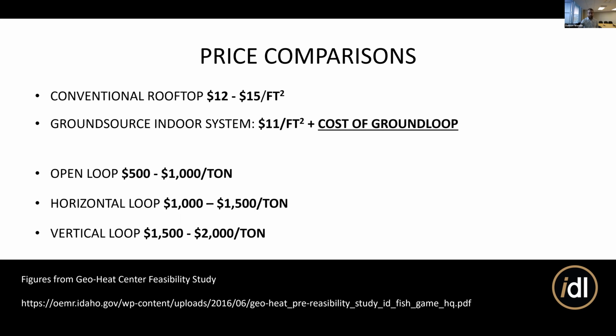A horizontal loop, those slinky systems that can be spread out at 6 to 10 feet underneath the ground, those were $1,000 to $1,500 per ton. And then the vertical boreholes were $1,500 to $2,000 per ton. The highest energy savings came from the vertical loop because temperatures were just more consistent there for that particular application. The system that came with the highest payback was actually the horizontal loop system. But these are some things to keep in mind.